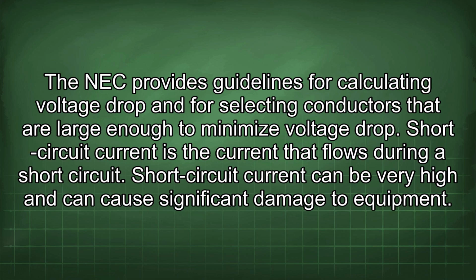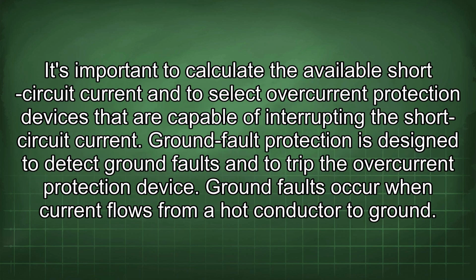Short circuit current is the current that flows during a short circuit. Short circuit current can be very high and can cause significant damage to equipment. It's important to calculate the available short circuit current and to select overcurrent protection devices that are capable of interrupting the short circuit current. Ground fault protection is designed to detect ground faults and to trip the overcurrent protection device.